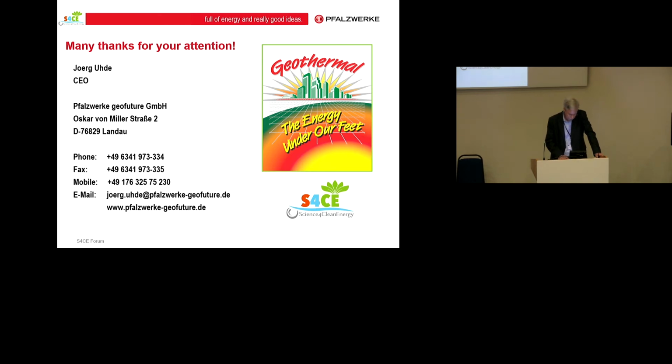And Landau had a problem with the permeability of the reinjection well, and to enhance the permeability of this injection well, a stimulation process was done. So water was pumped with high pressure into the reservoir to enhance the permeability of the reservoir, and this caused a seismic event 2 weeks later of about 3 to 3.5 on the Richter scale, in combination with a supersonic sound wind when the air was blown out of the well. And this was the initial event to cause public initiatives against the geothermal. And basically this was another reason to have this multilateral completion with our reinjection well that my predecessors have drilled a sidetrack there.